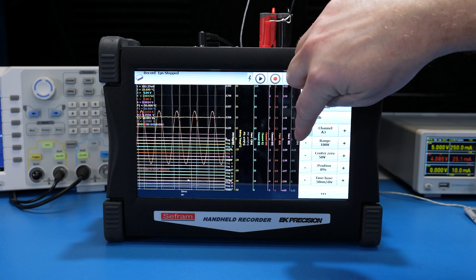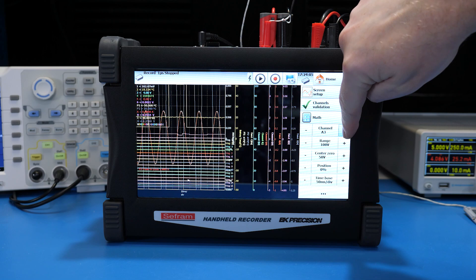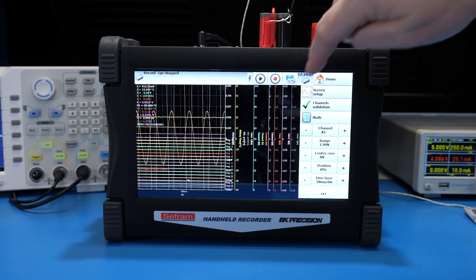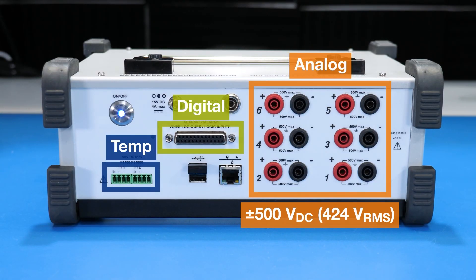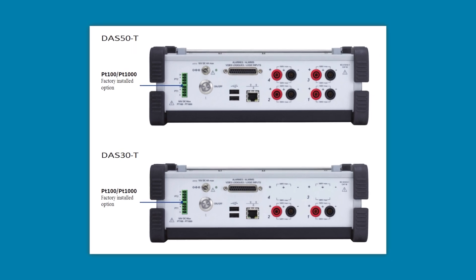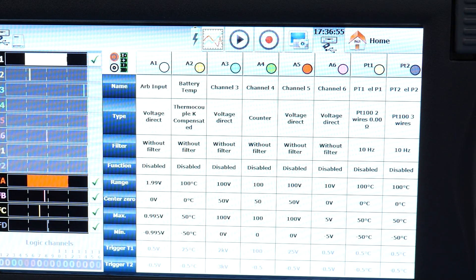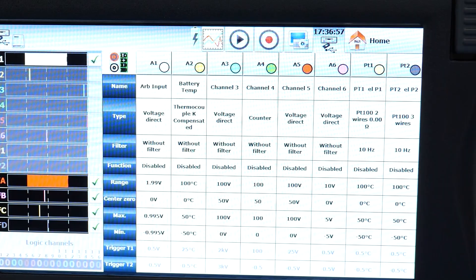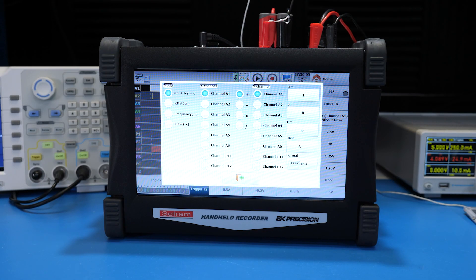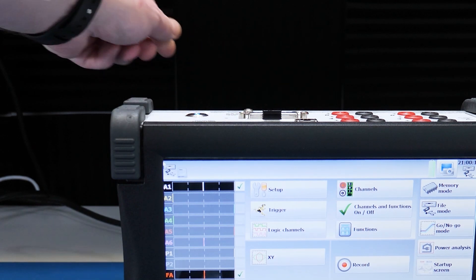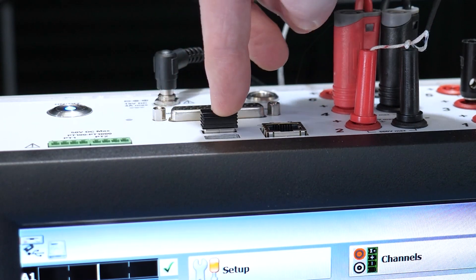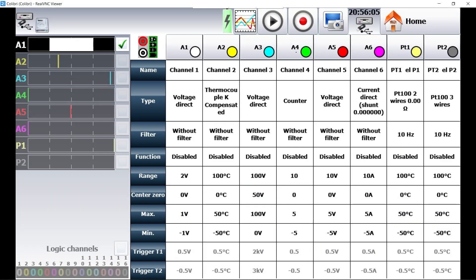Overall, I think as a multi-purpose data logger, the DAS 60 has the right set of core features. There are plenty of input options available, even on the two-channel version. Those inputs can represent any practical quantity that is measurable as voltage. There are powerful measurement and waveform math capabilities, even if I think they're named wrong. The combination of built-in battery and remote access via WiFi or ethernet means you can place the unit anywhere in a facility or on a site and check in to see what is going on.